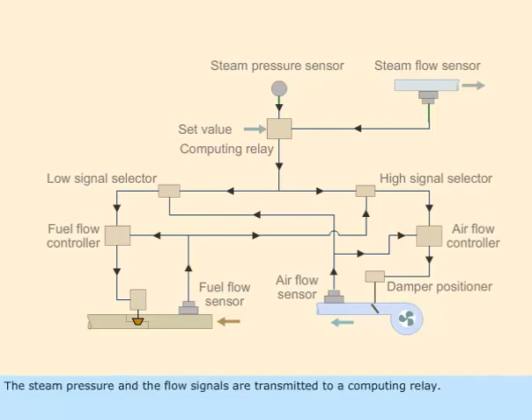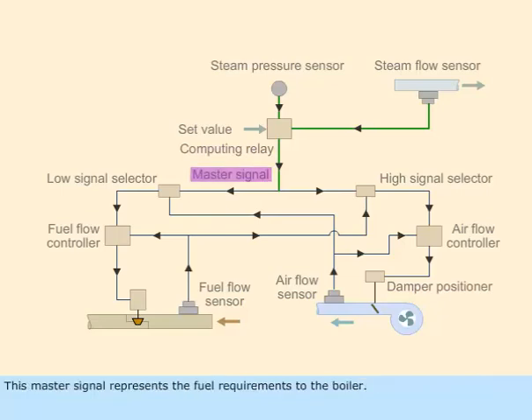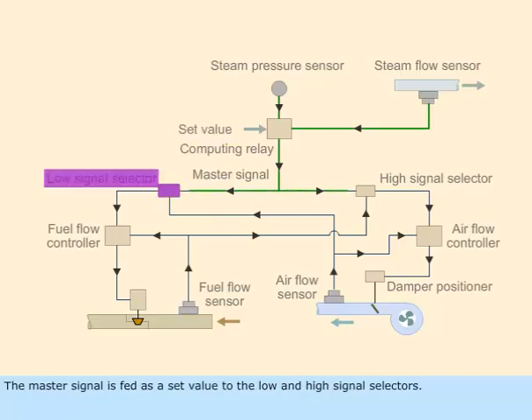The steam pressure and the flow signals are transmitted to a computing relay. The computing relay generates the master signal depending on the load of the boiler. This master signal represents the fuel requirements to the boiler, and is fed as a set value to the low and high signal selectors.